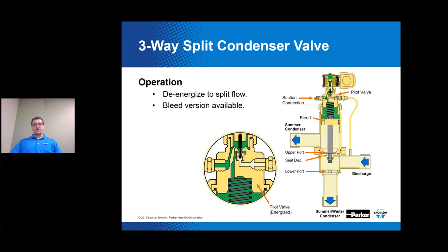Typically your split condenser valve is controlled by an ambient temperature control set for a specific outdoor temperature, and it can also be controlled by a high side pressure control device. The valve depicted here is our version containing the bleed port. Some variations do not have the bleed port — the bleed port allows refrigerant to transfer back from the idle condenser through the piston and pilot assembly back to the suction header.